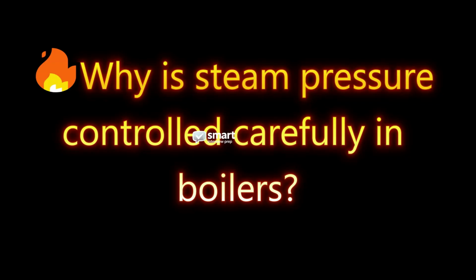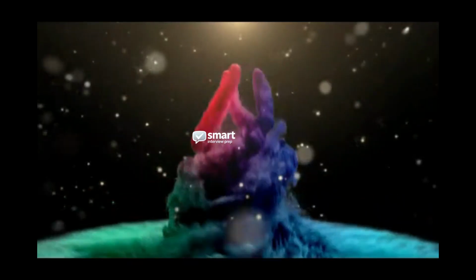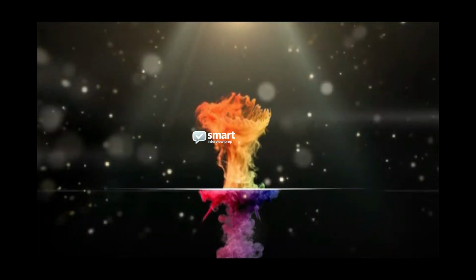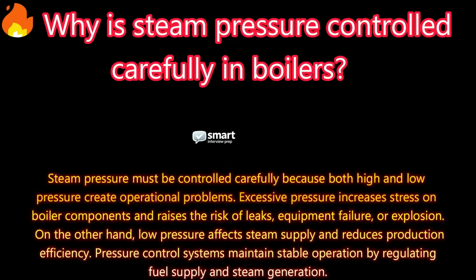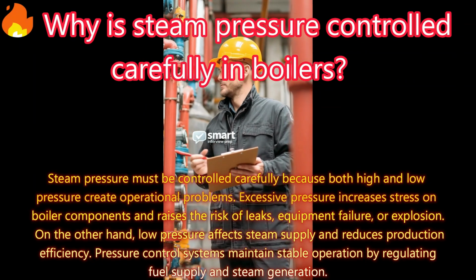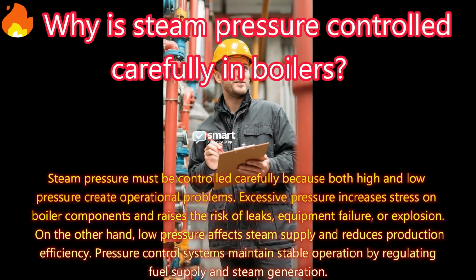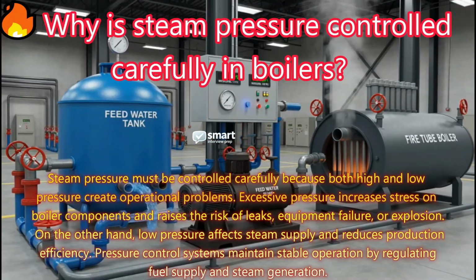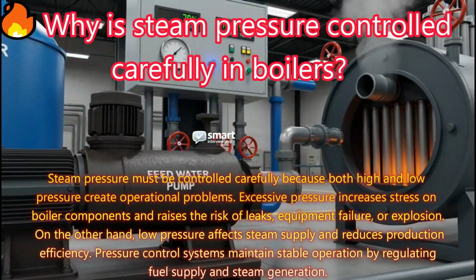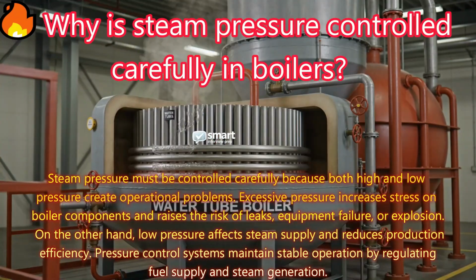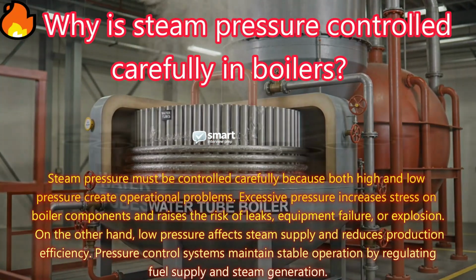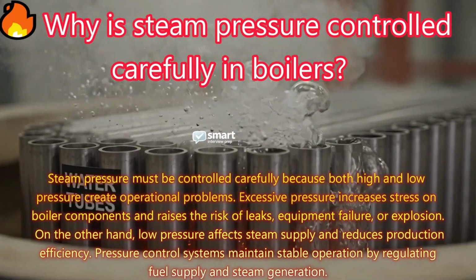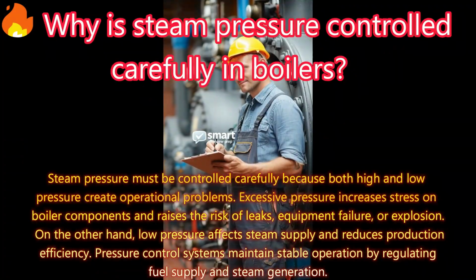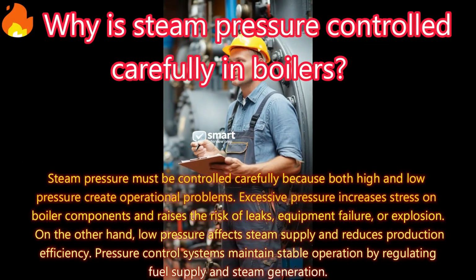Why is steam pressure controlled carefully in boilers? Answer: steam pressure must be controlled carefully because both high and low pressure create operational problems. Excessive pressure increases stress on boiler components and raises the risk of leaks, equipment failure, or explosion. On the other hand, low pressure affects steam supply and reduces production efficiency.